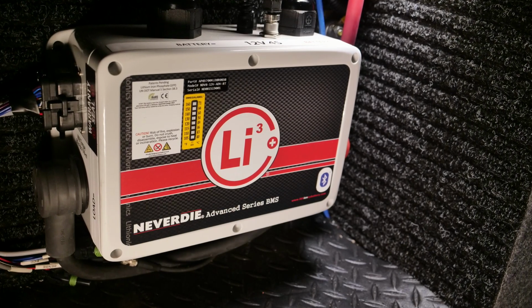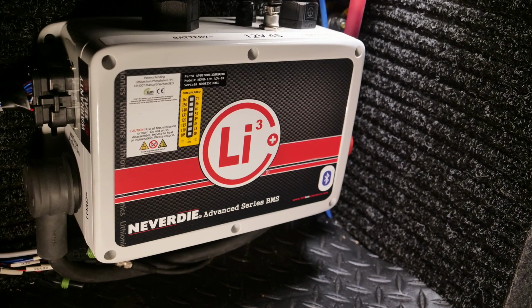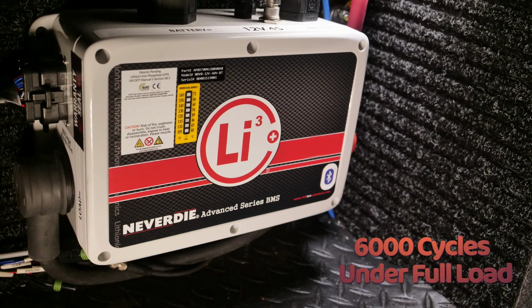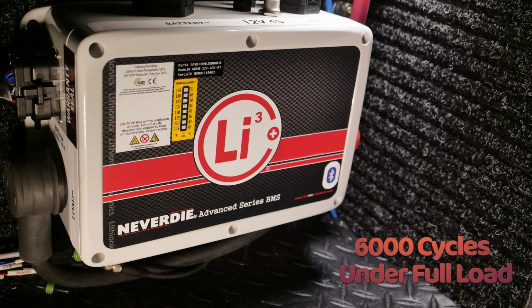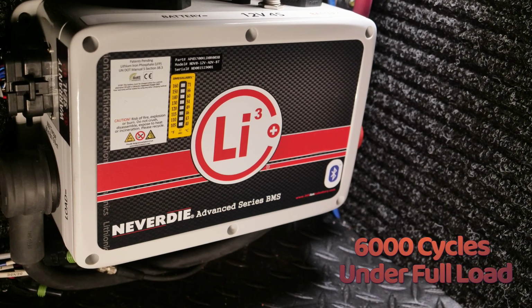In order for the BMS to meet UL 1973 standards, these contacts were required to open and close under full load for 6,000 consecutive cycles without a failure.